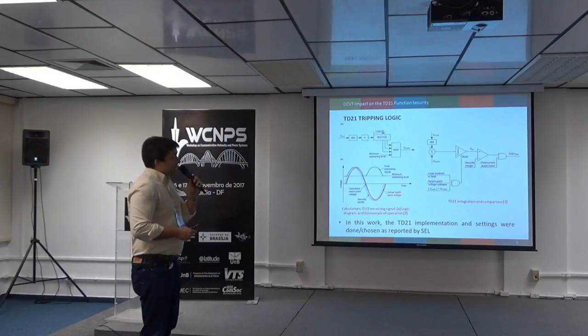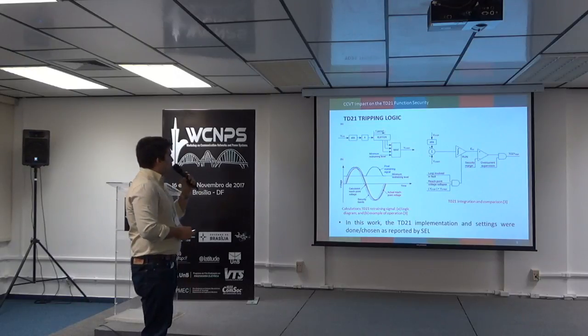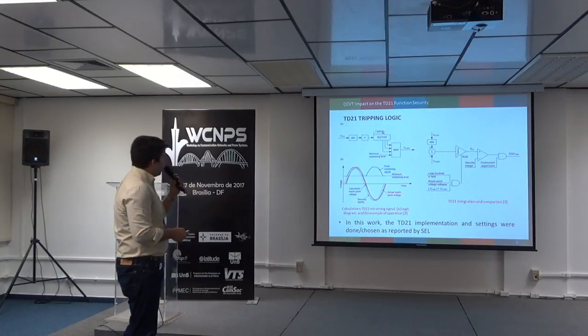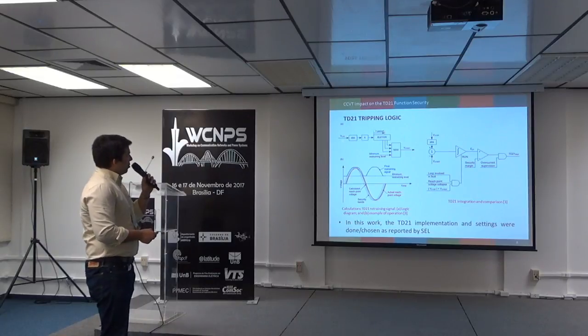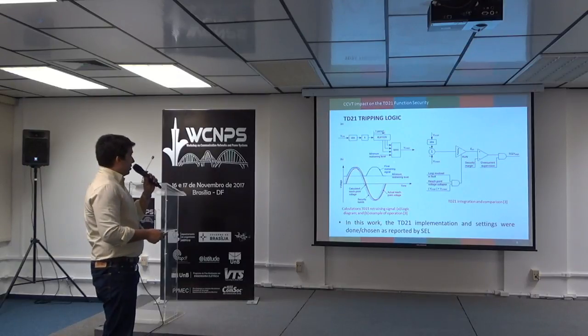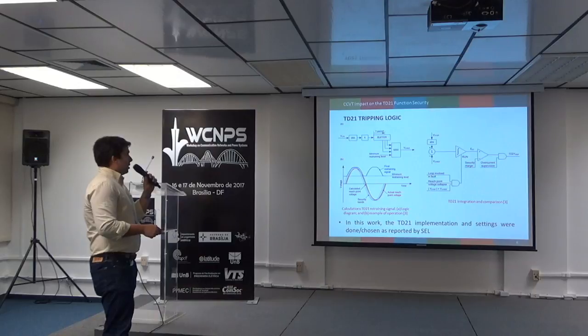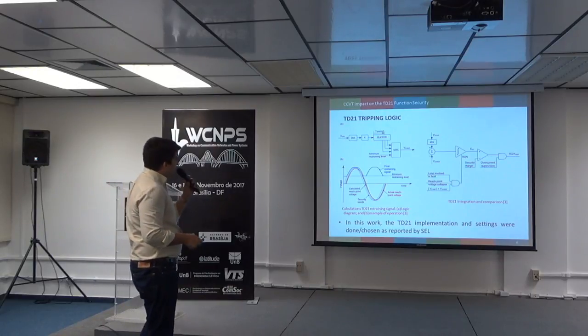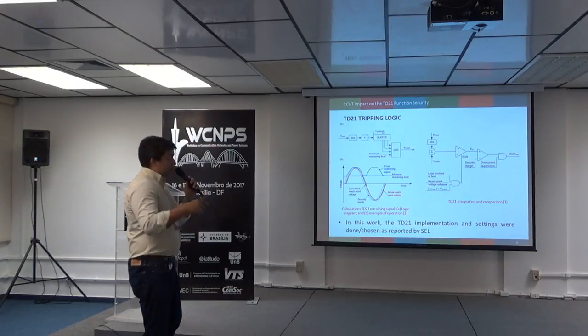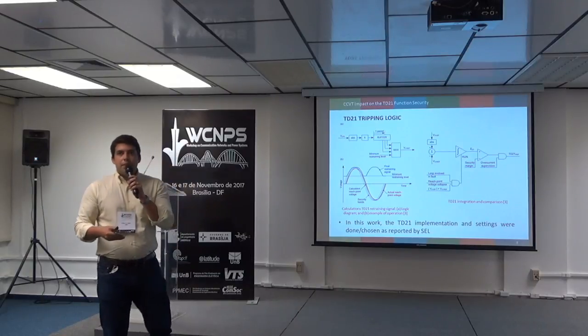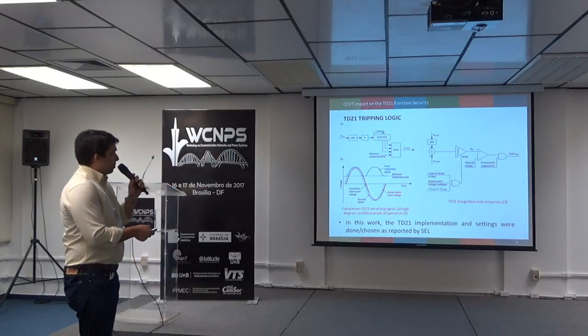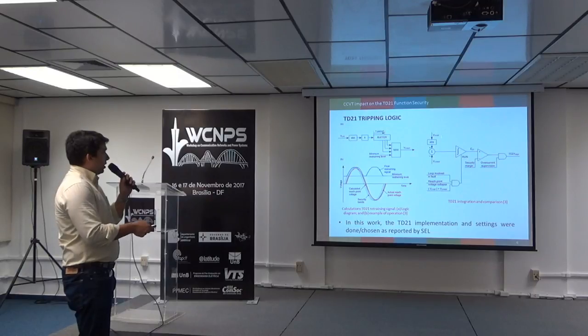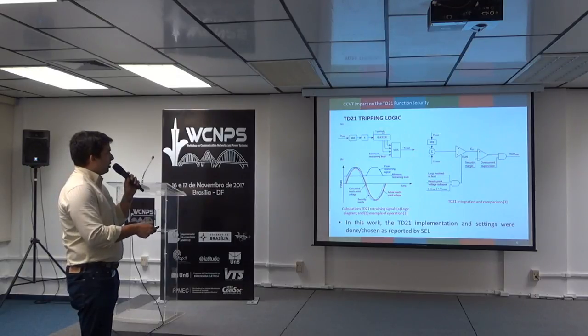Well, for the sake of security, the TD21 uses some additional security conditions. We take this pre-fault voltage and analyze some delayed samples and compare them, using a minimal restraining level to obtain a final restraining signal, which will be compared with the operating signal.